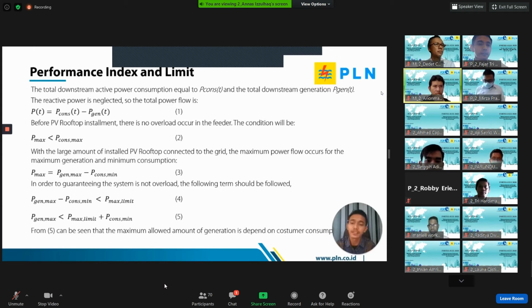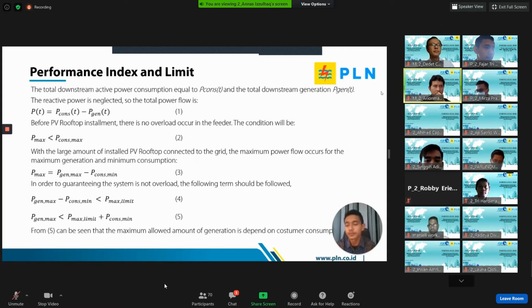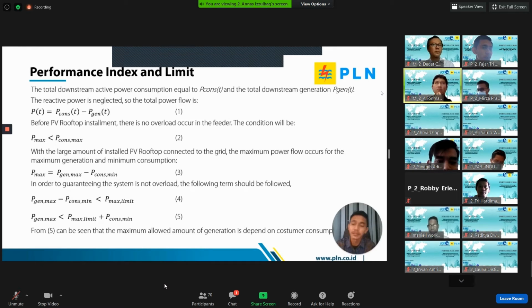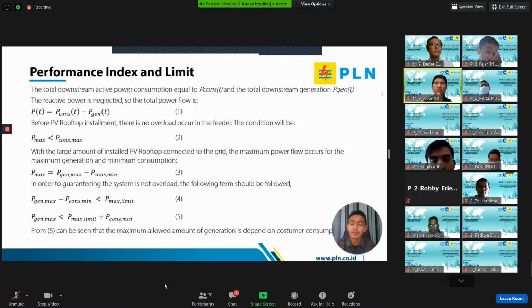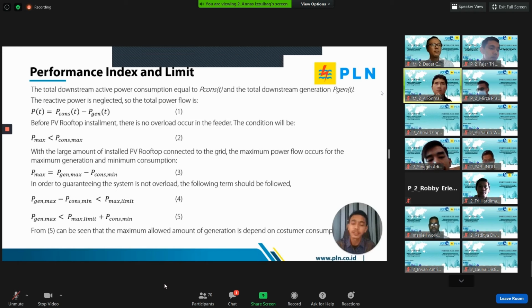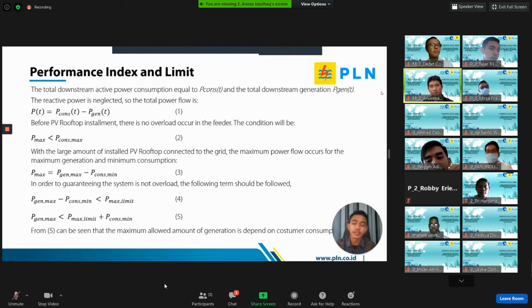In order to guarantee the system is not overloaded, the following terms should be followed. P generation maximum minus P consumption minimum is less than P maximum limit. And then P generation maximum is less than P max limit plus P consumption minimum. From equation 5, we can see that the maximum allowed amount of generation depends on customer consumption.